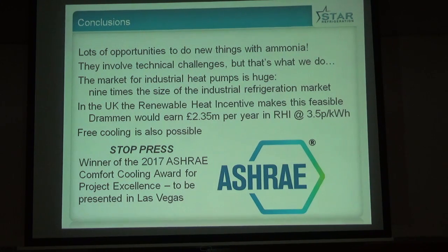So the supply temperature, they'll raise it all the way up to 90 and then switch the heat pump off and allow it to come all the way back into 70 and warm it up. I forget the length of the loop here, but it's easily 6 miles of large diameter pipework. There's a very long thermal lag in the system.